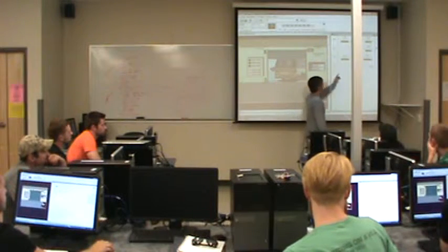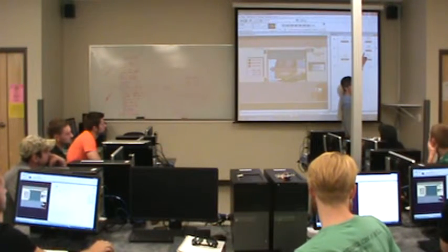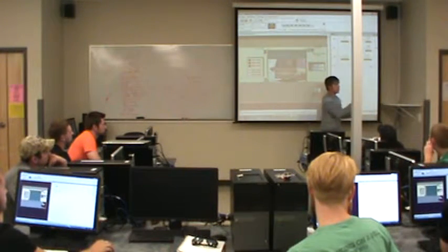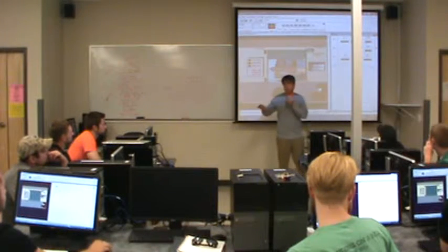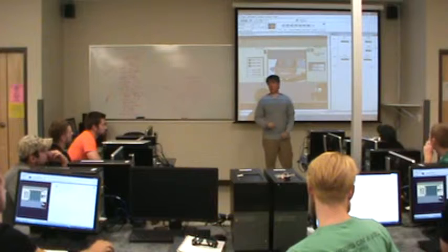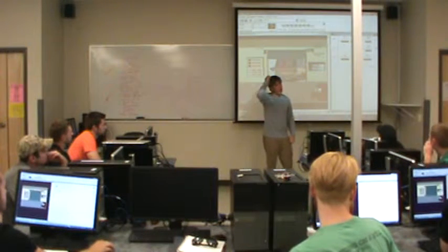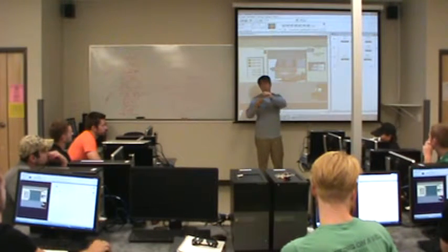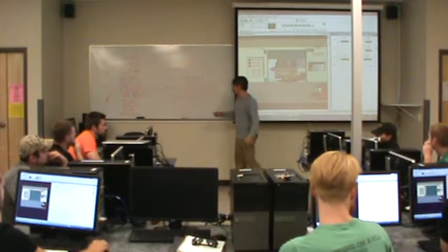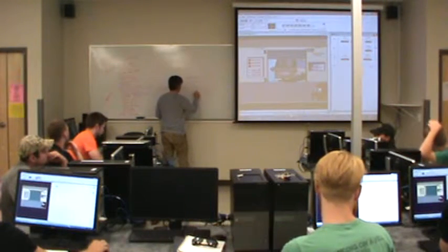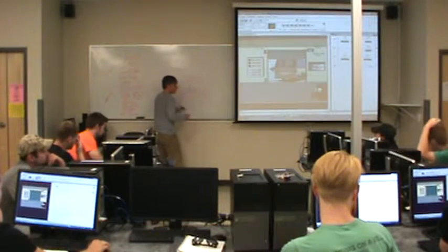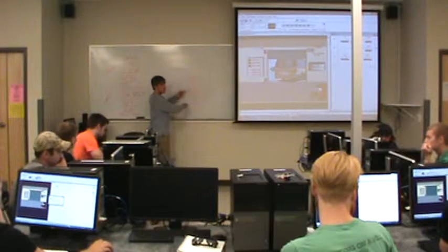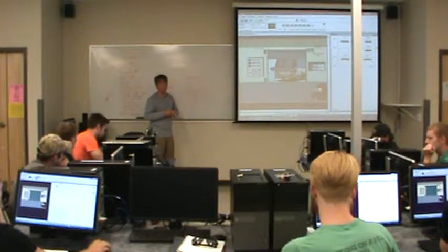Because what will happen is the PLC will calculate what the output should be in one place, which is what you're thinking about, and say, well, that output should be on. And then somewhere else in the code, it calculates it again and says, oh, it should be off. And it'll actually write it, when it actually finishes the evaluation, it'll write it as off. And you'll be scratching your head going, I know that rung's calculated to be on, I can see it, what's going on? The problem is you reference the same output two different places. Okay, so you basically said, okay, computer, x equals 5, and then later on you said x equals 7, and when the computer tells you x equals 7, you say, why didn't you say x equals 5? Because you told it to do two different things in two different places, it just does whatever the last thing was that you told it to do.